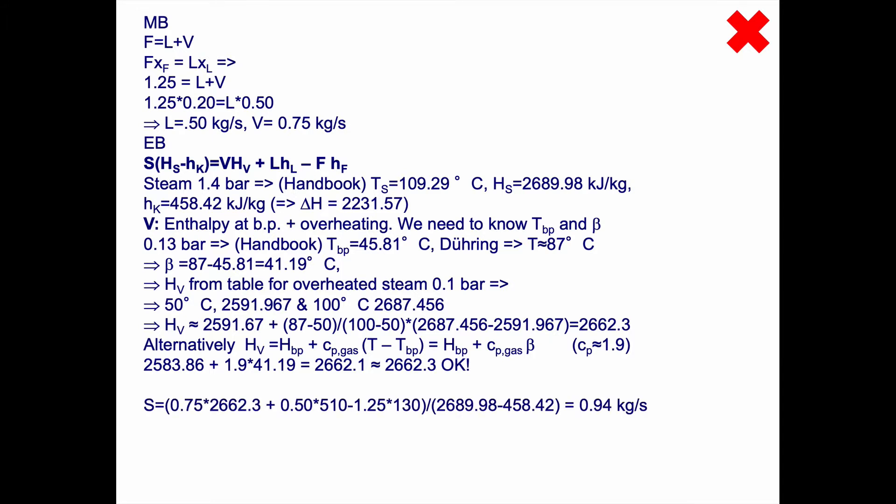I calculate S using this equation. We have V = 0.75, L = 0.50, and F = 1.25. Then I multiply with the respective enthalpy and divide by the difference between hs and hk. I get a steam consumption of 0.94 kg per second. So that's our answer.